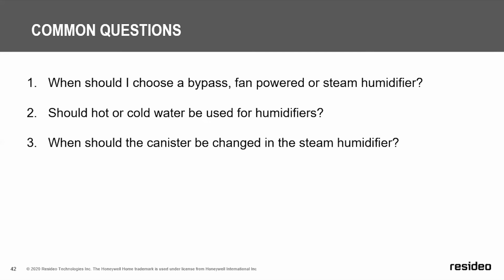When looking at bypass humidifiers and fan-powered humidifiers, some people recommend hot water. I personally don't believe that the advantage you get from using hot water in fan-powered or bypass offsets the cost associated with using hot water, since so much of that water goes down the drain at the end of the day. I ask people to think about it this way: when you're washing your hands and you go to the hand air dryer, do your hands dry faster because you used hot water or cold water? It really doesn't make a difference. It's the temperature of the air. That's a great analogy.